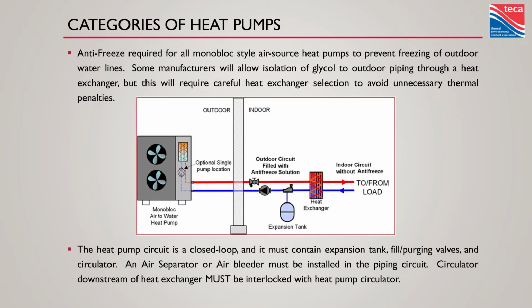So glycol. Glycol means that you're going to have to increase your flow rates because glycol transfers less heat than water does. And it means you're going to have to increase the size of your pumps because it's significantly more viscous than water. So you're dealing with higher pressure drops.